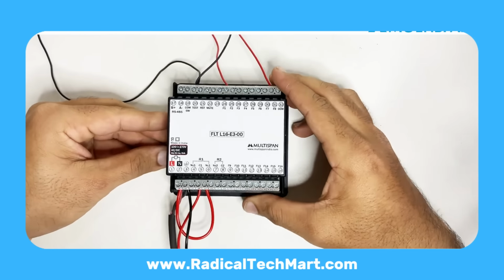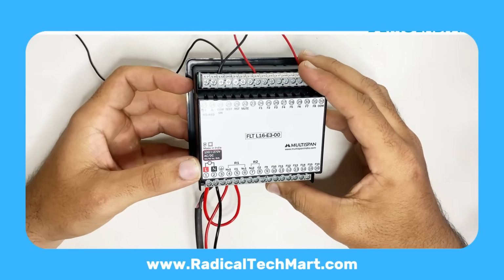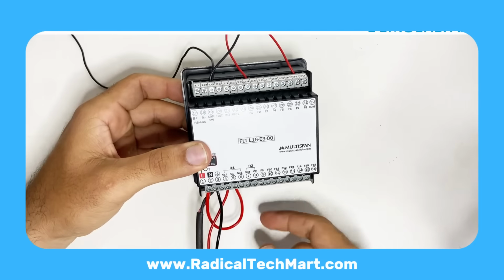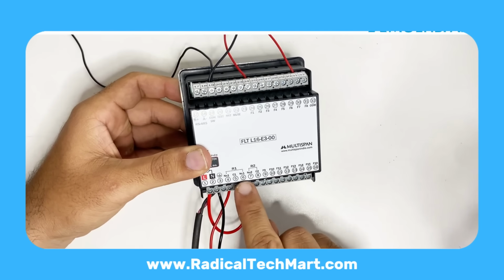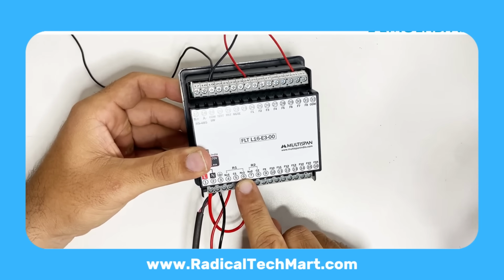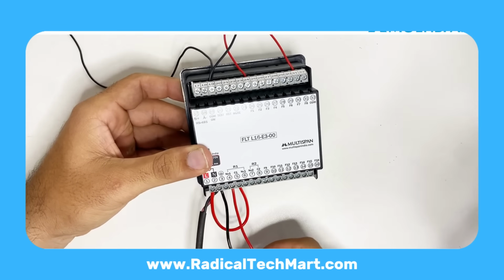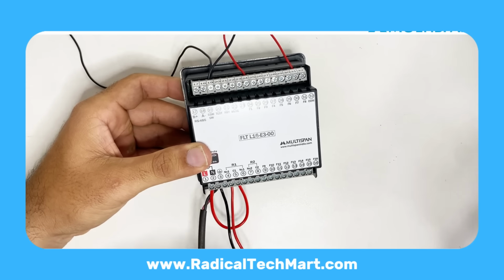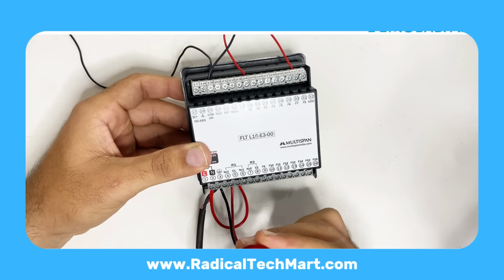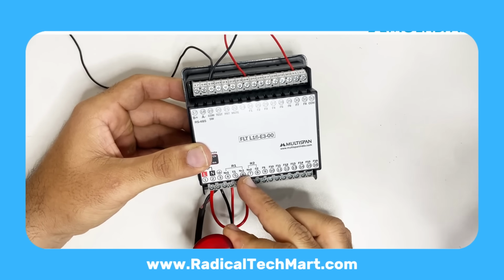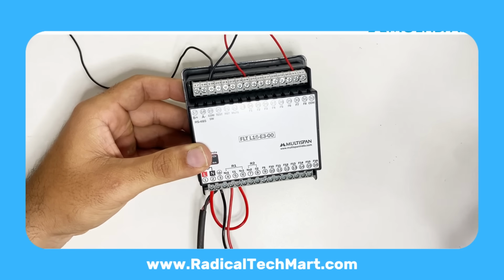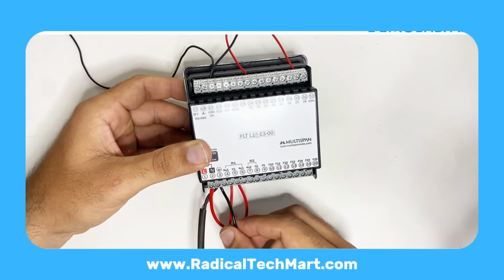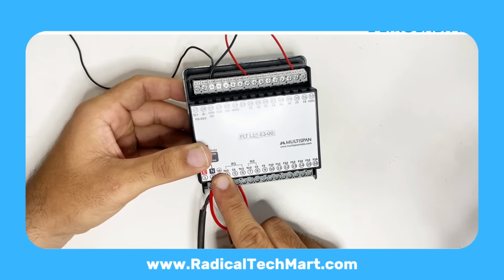On the back side, we've given line and neutral on terminals 1 and 2. From terminal 1, line, we have taken a loop to C1, which is the common for relay 1, alarm relay. From the NO, normally open, contact, we have taken a wire to the LED. So whenever relay 1 turns on, the LED will glow. The LED's neutral is connected back to terminal 2, neutral.